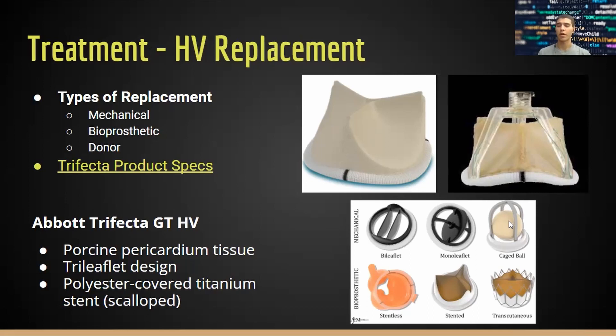The cage-ball design had pros and cons — it provided reasonable blood flow for one of the early prototypes, but involved complications such as lysing of blood cells and accelerated clotting, which you don't want on a device. Further developments led to the monoleaflet and bileaflet mechanical heart valves, which are made of pyrolytic carbon to prevent clotting on the device.